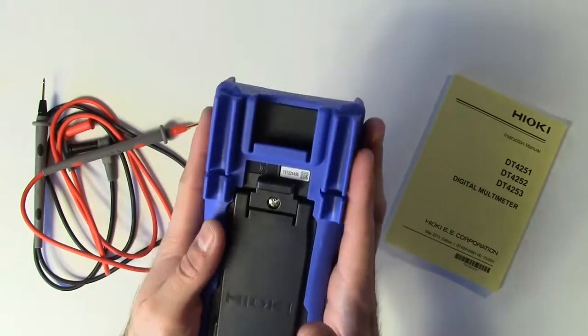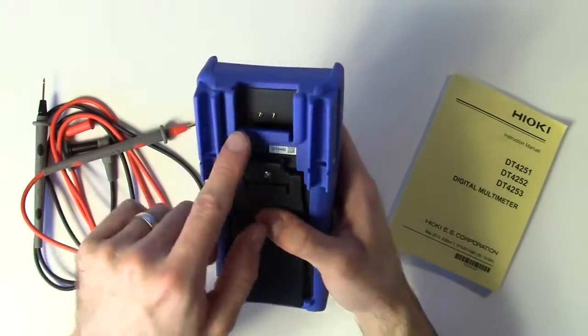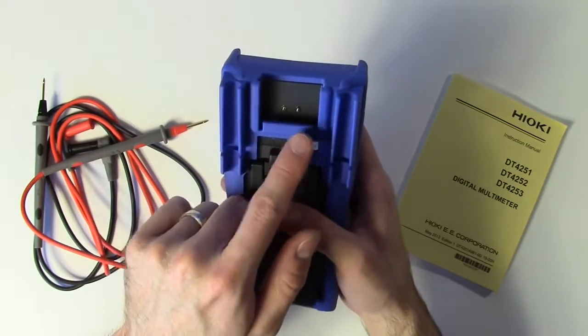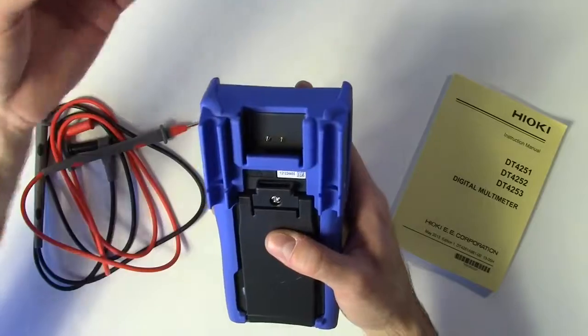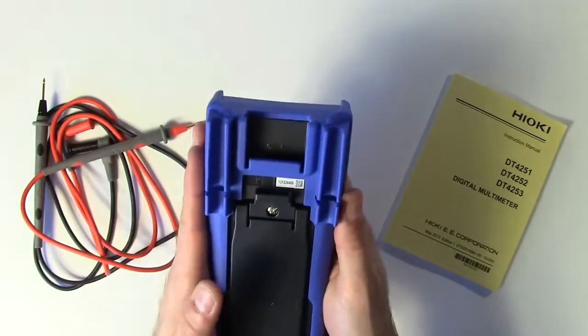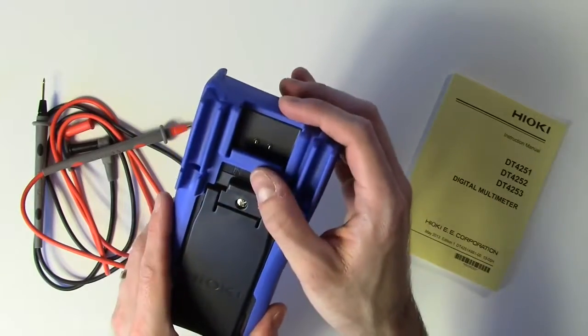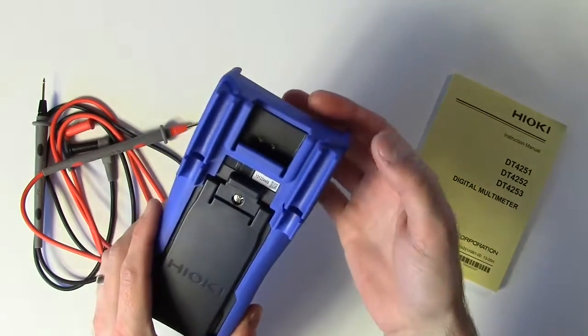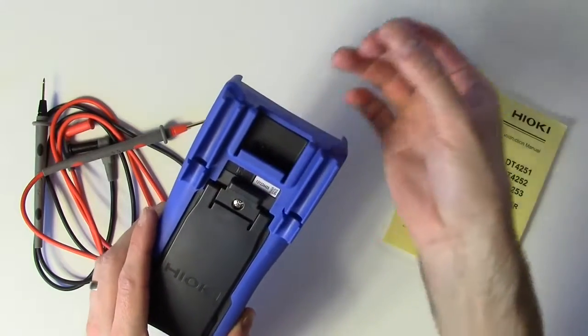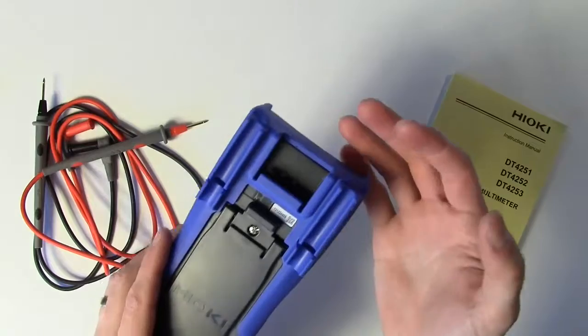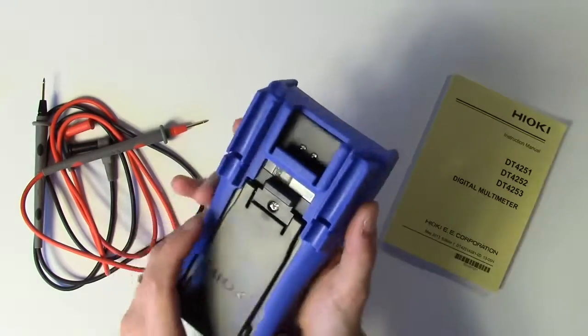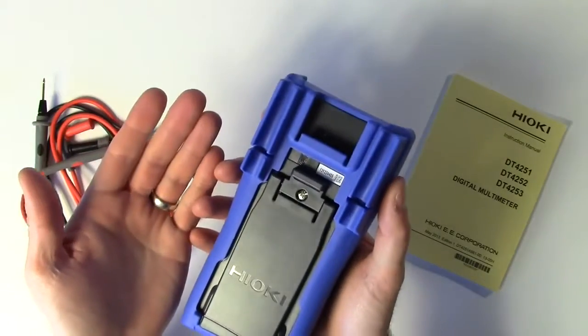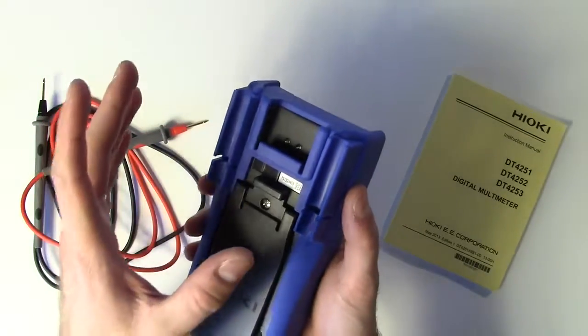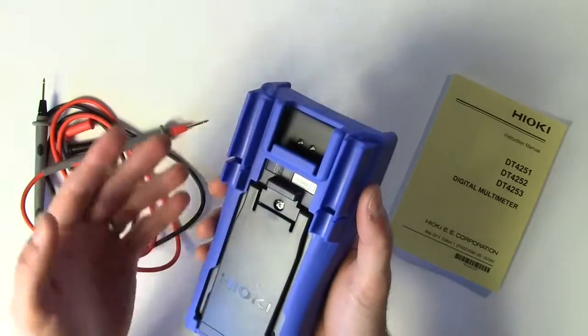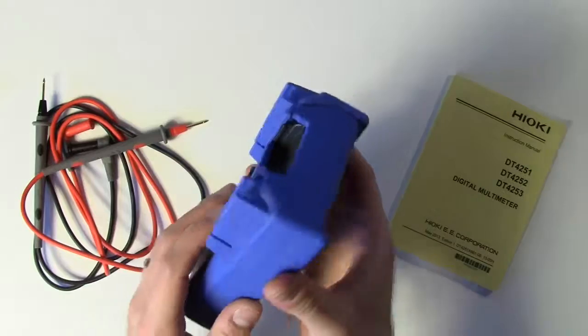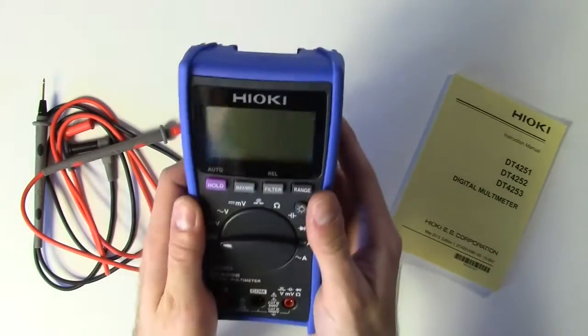It seems like a lot of the accessories for this meter are optional. For example, it's also got the data logging capability. These are your infrared transmitter and receiver functions. It's a separate module for the cable. Now, I will give Hioki some credit in that the optional module is native USB based. It's of course optical based, so you don't fry your computer, but the module plugs in and then it's a USB cord that goes directly into it. So you don't have to deal with one of those stupid USB to serial adapters. The cable also comes with the software. I don't have the cable and I don't have the software, so I can't review it. But at $100 for just that cable and software bundle, you're going to want to really think about whether data logging is important to you or not if you're considering this meter.